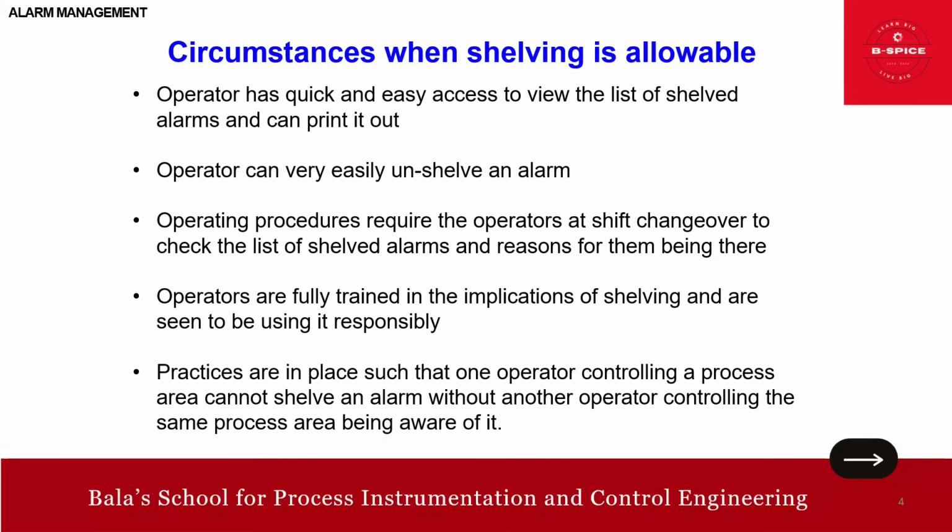Then at the planned time of unshelving, either the operator might be prompted to unshelve the alarm or the alarm might be automatically unshelved. A further feature is often provided as a default, like maximum shelve time allowed, after which the alarm is automatically unshelved.